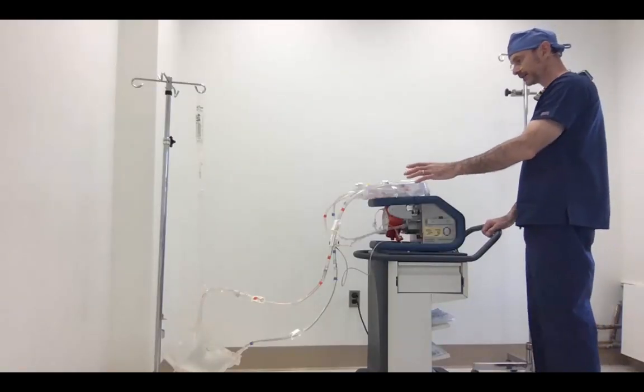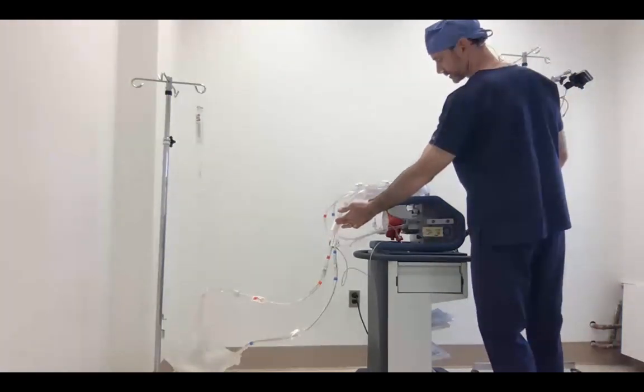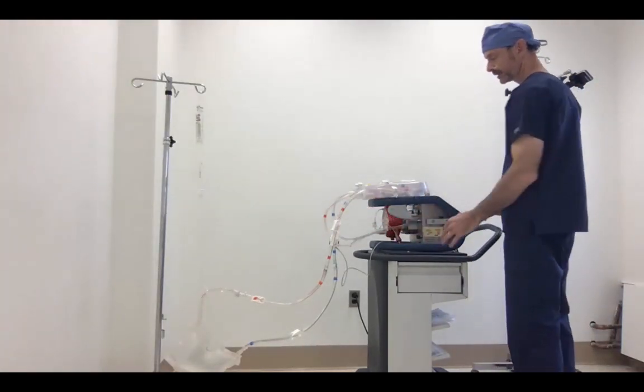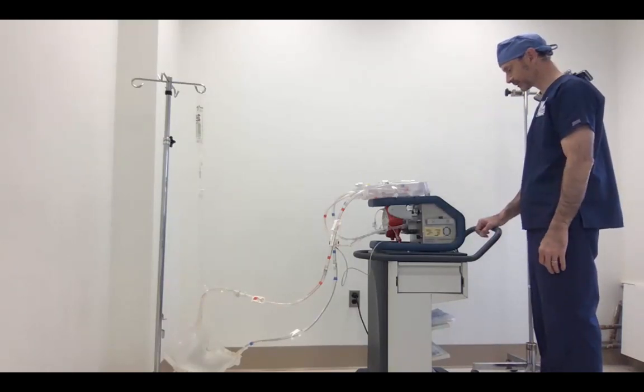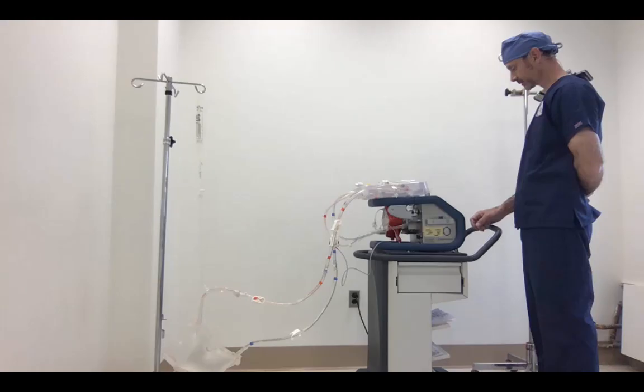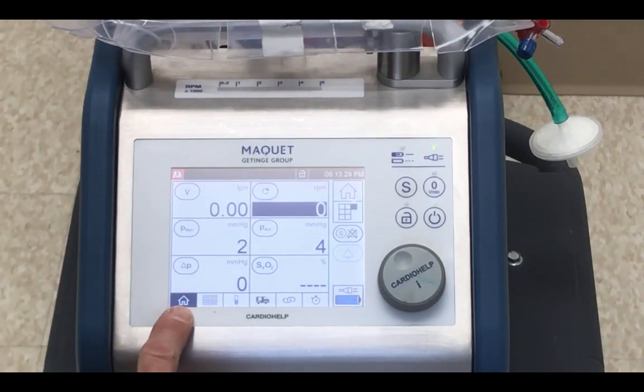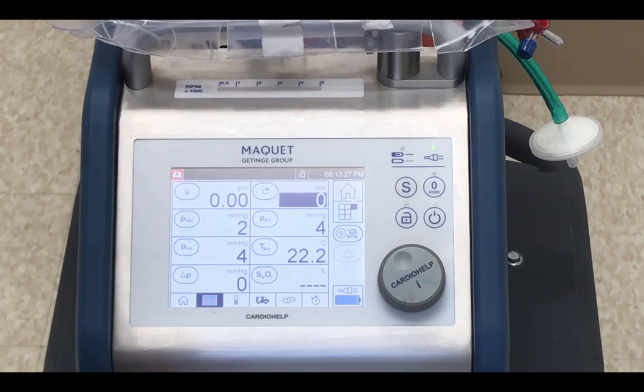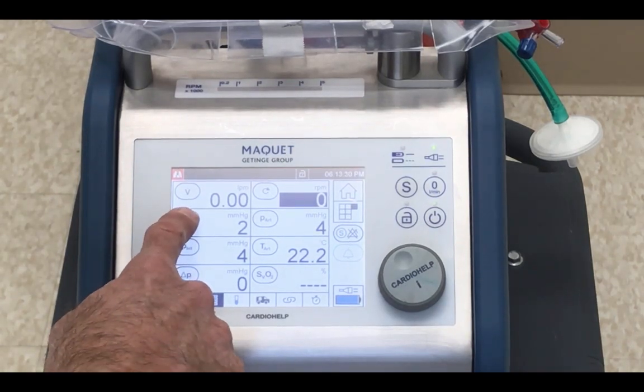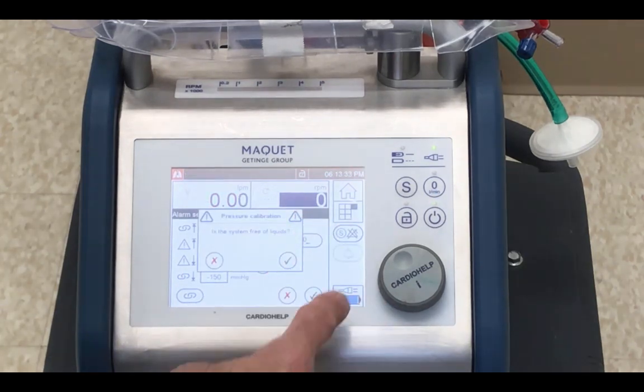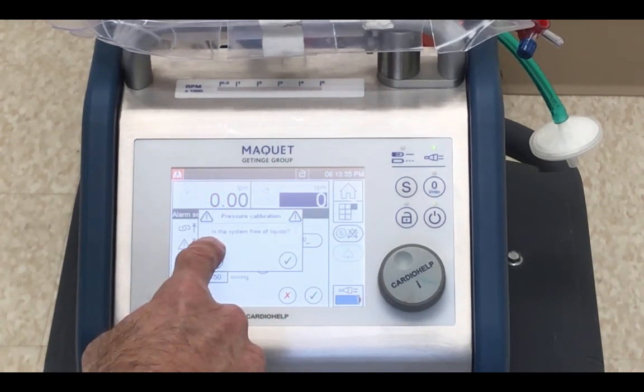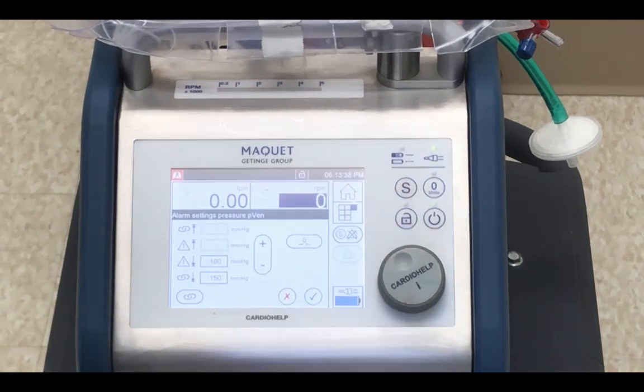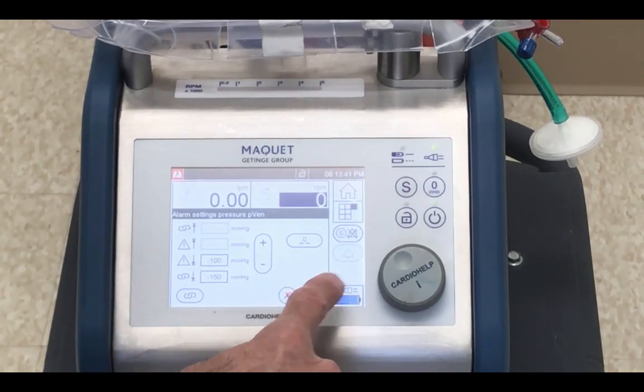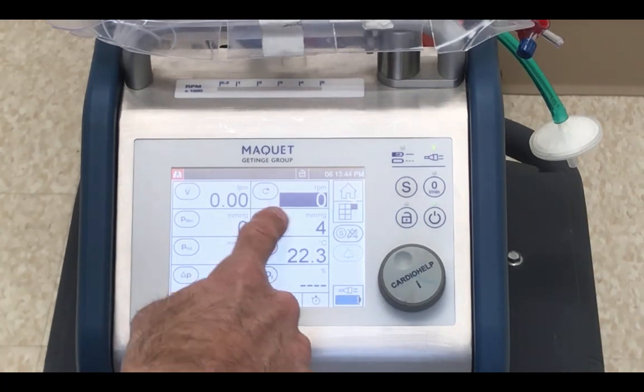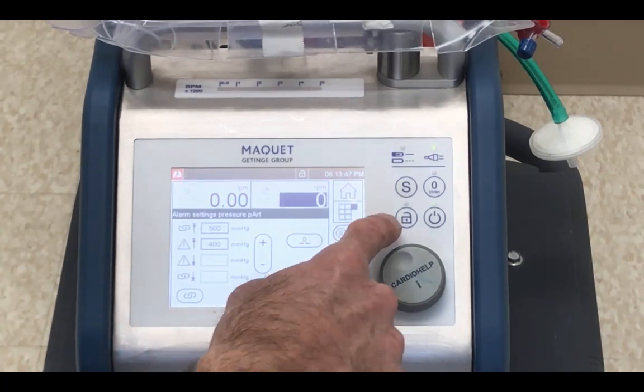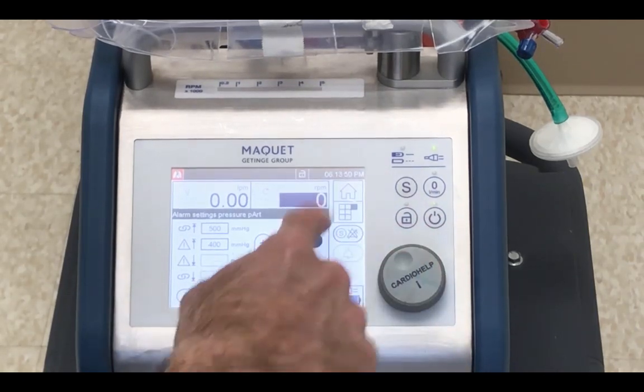And before we add any fluid on this side of these clamps, and while this system is still just full of air, that's the best and recommended time to zero your transducers. So let's go through our menu items, and we're going to leave the home screen. We're going to go to the screen that has all 3 pressures on it. And we're going to find one at a time. Go to the pressure venous, tell it to zero. And it says, is the system free of liquids? Yes, it is. We've zeroed that one. And then P arterial. Zero that one.